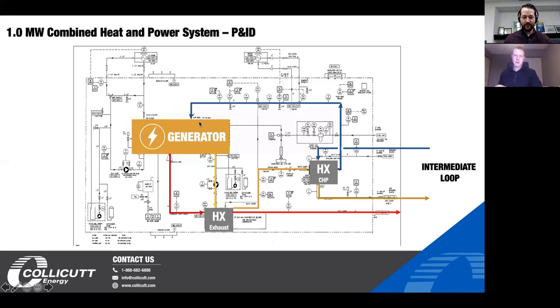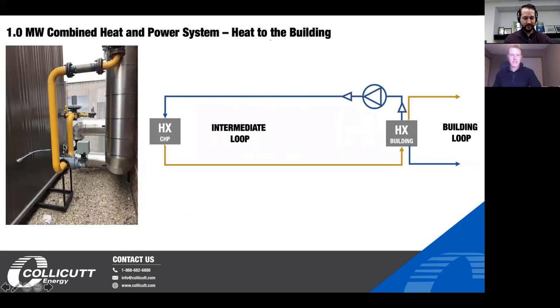So then how is the heat being transmitted from the CHP that you saw in the photo before to the building? On the outside of the CHP, you'll see these two insulated lines. What we've got outside the modular enclosure is these two 4-inch lines. I know those don't look like 4-inch lines. They've been insulated because here in Canada, we get down to minus 35 degrees Celsius, so they need to be insulated. One's the supply, I believe this is the supply and this is the return line, supply to the building and return back. It's a 4-inch line with 3 inches of insulation to get a 10 to 12 inch outside cladded line.